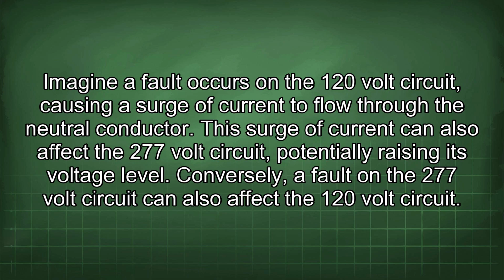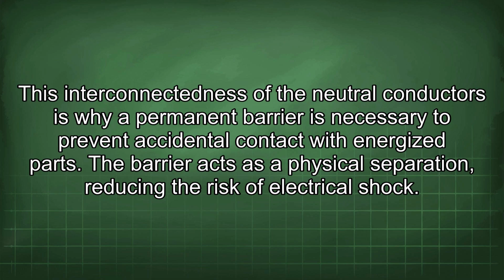This surge of current can also affect the 277 volt circuit, potentially raising its voltage level. Conversely, a fault on the 277 volt circuit can also affect the 120 volt circuit. This interconnectedness of the neutral conductors is why a permanent barrier is necessary to prevent accidental contact with energized parts. The barrier acts as a physical separation, reducing the risk of electrical shock.